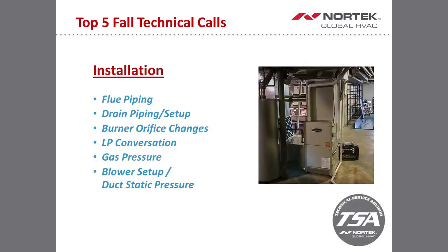The first question we ask is, what are the dip switches set to? Generally, they're all in the off position, which is the lowest possible blower setting. The main reason we don't preset anything is because we don't know the application of the furnace it's going in. On the variable speed side, you're able to pick a CFM, and the blower motor will achieve that. It'll ramp up or ramp down based on your duct static pressure.